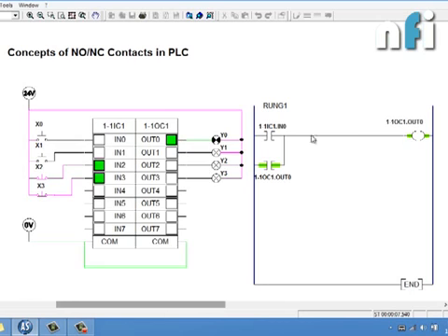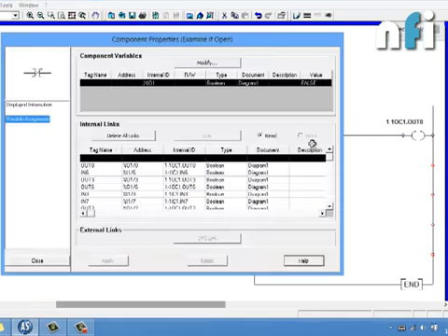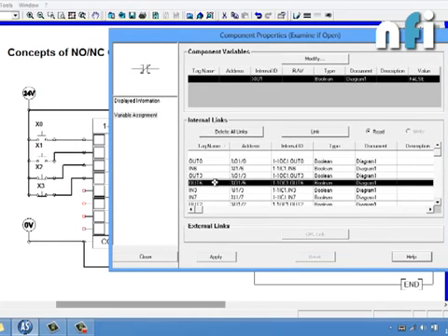Now I want to stop this latching, I want to unlatch this circuit using NO switches, using this switch. How can that be done? You can see that this switch is used to actuate IN1. So to turn off this output coil, I have to introduce the NC of this IN1. Let's see what will happen. Let me connect that. This comes here, and this will go here, and I'll give it a tag of IN1 like this.